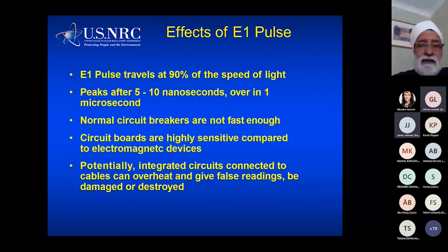E1 pulse travels at about 90% speed of light, peaks after about 5 to 10 nanoseconds, and it's over in about 1 microsecond. Obviously, our circuit breakers are not fast enough to protect us from that. Electronic circuit boards are sensitive, and potentially we can damage integrated circuits. And cables can overheat and give us false readings in our instrumentation and control systems.